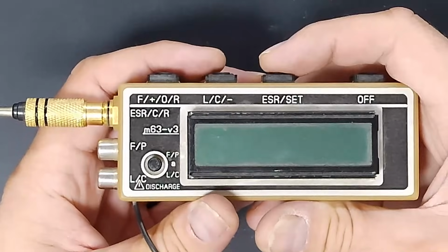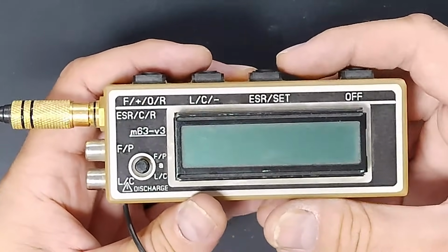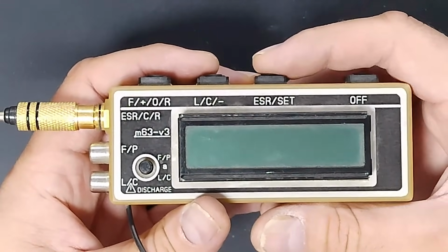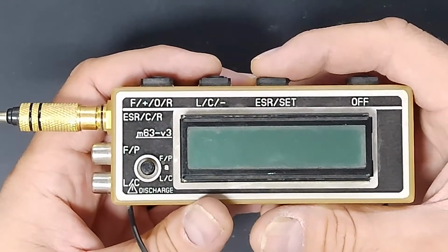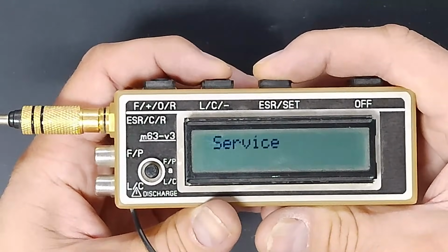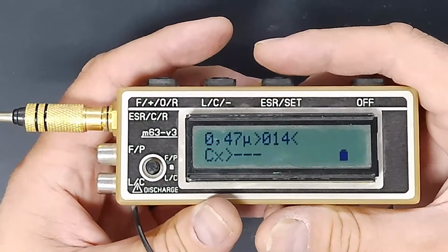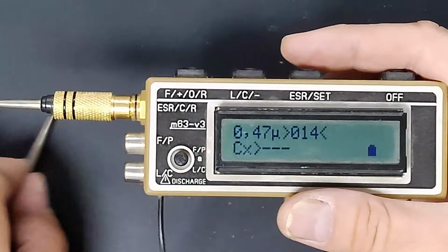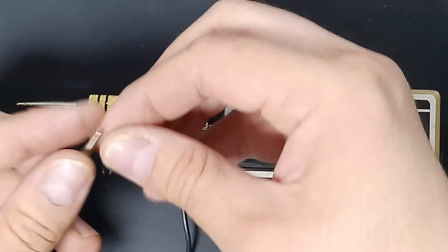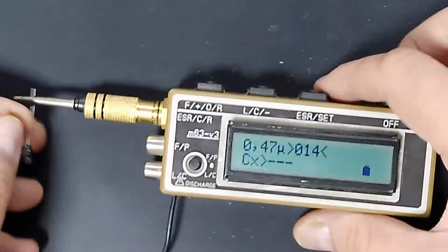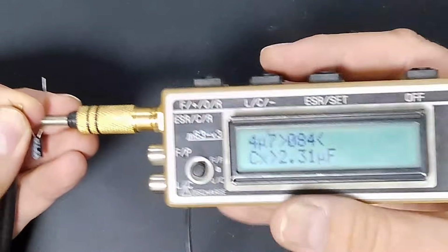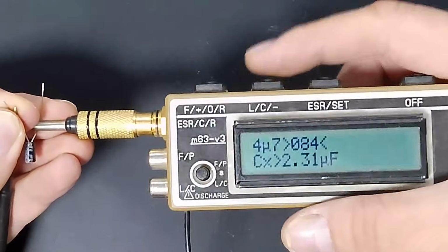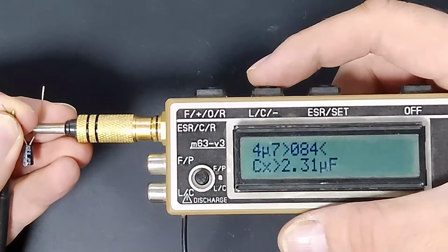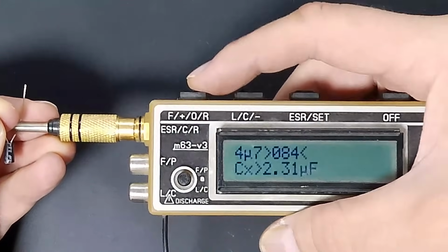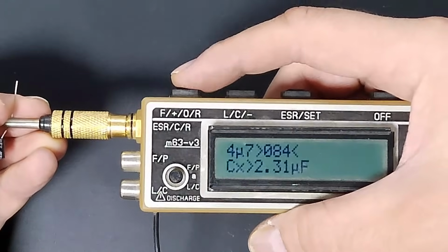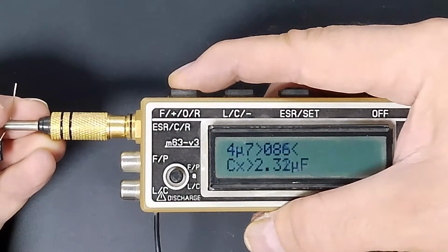So to calibrate this tester, from the off state you need to press and hold the set button, then the minus button, then release them. Then connect the testing capacitor and adjust until I have the same 2.32 microfarads.